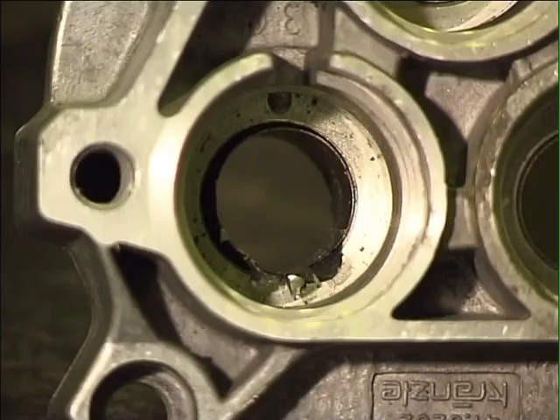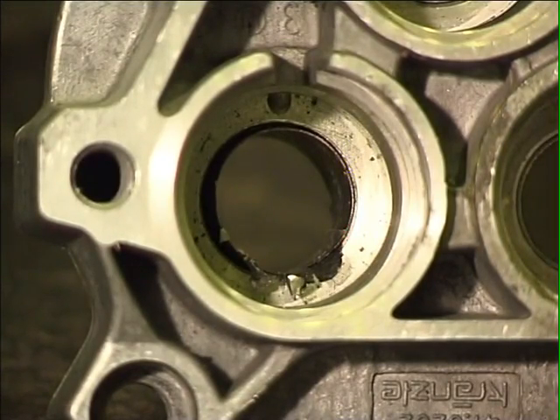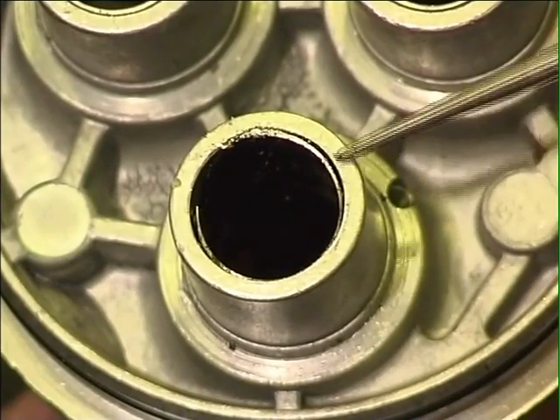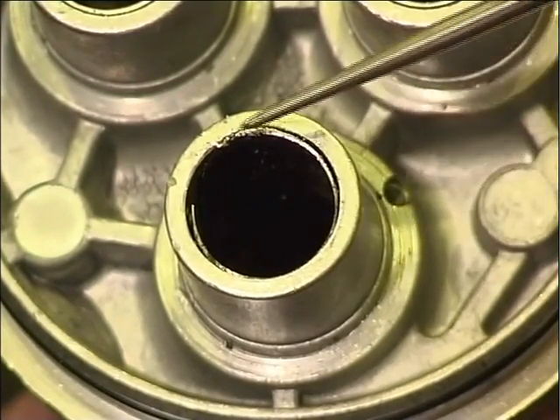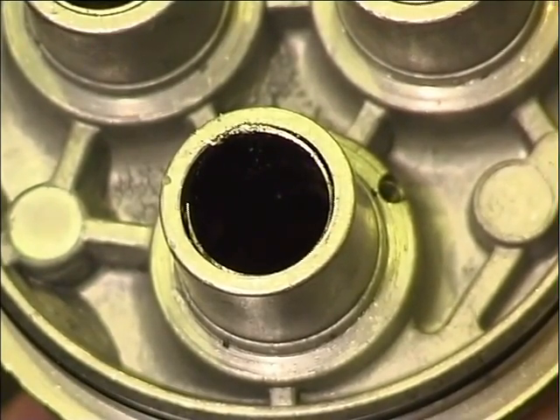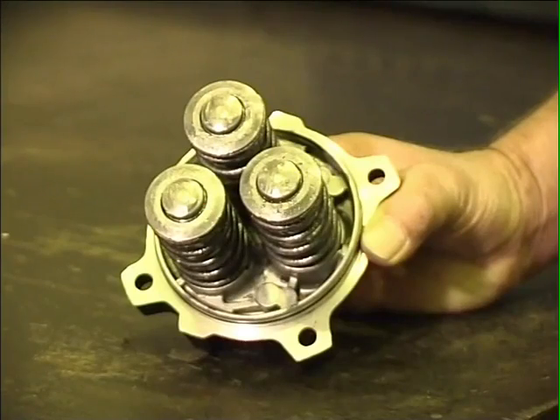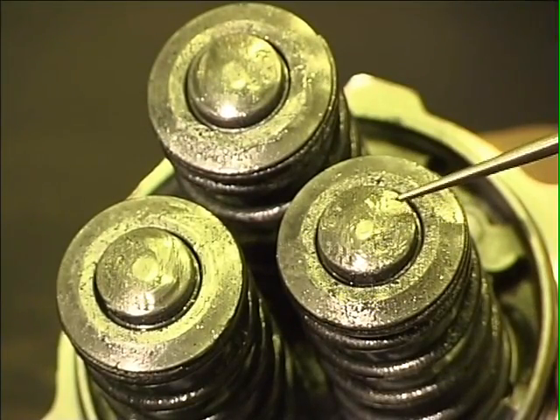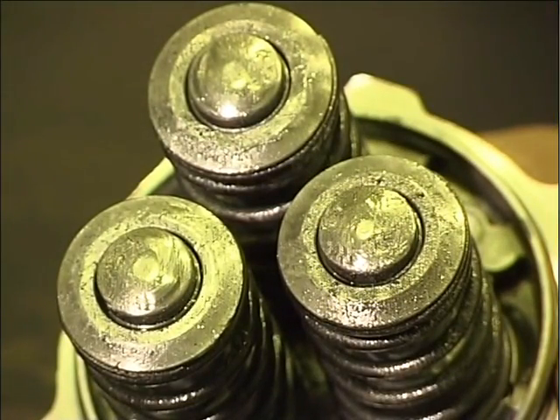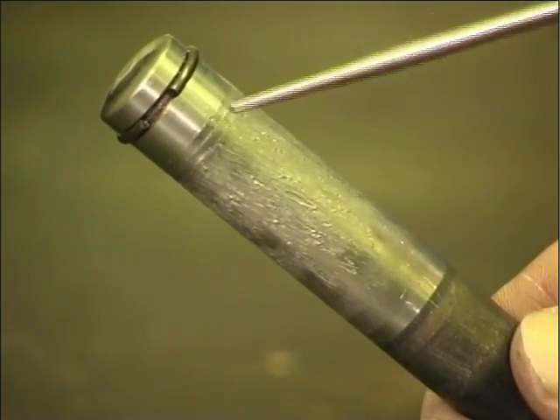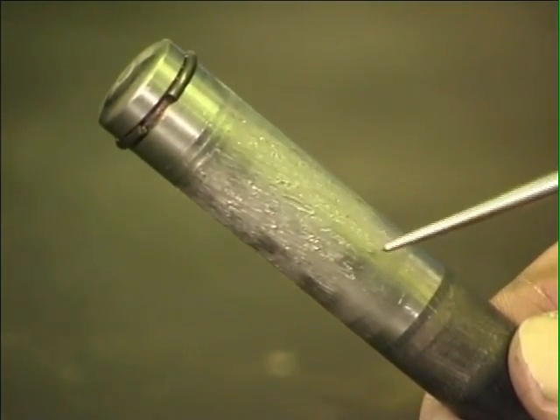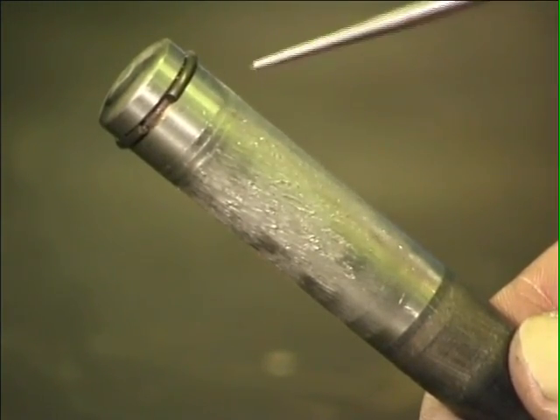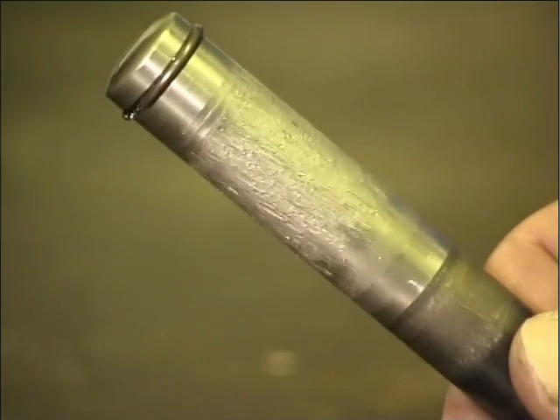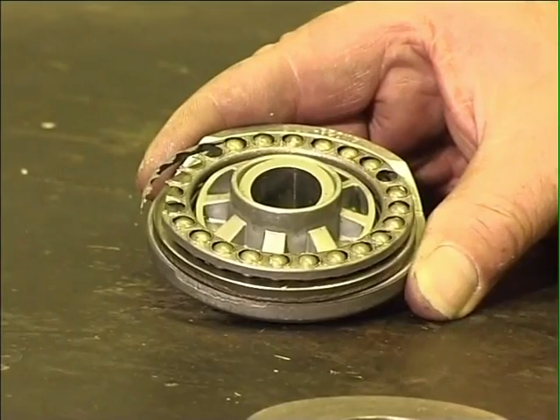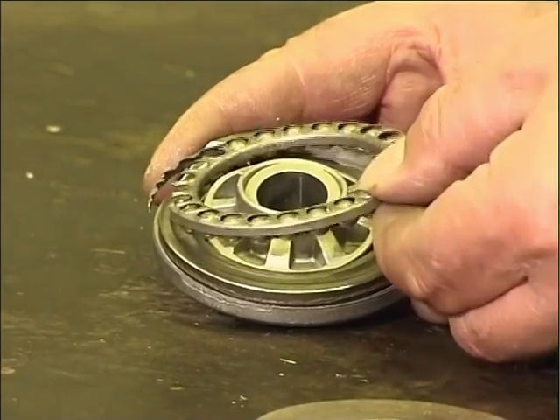If you do not change the oil seals in good time, transmission damages can also occur. Plunger guides can be destroyed, and plungers can be damaged. And as a result, the running area of the plungers can also be damaged. Condition of damages provides information about the causes. Cavitation can also lead to damages to bearing.